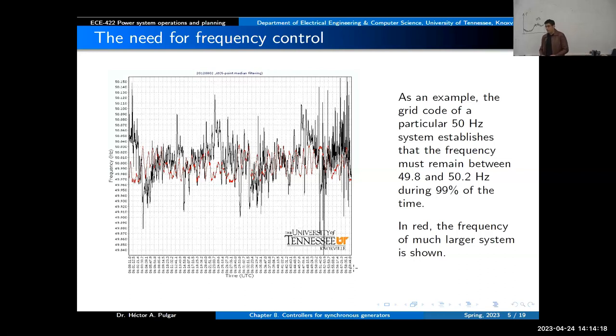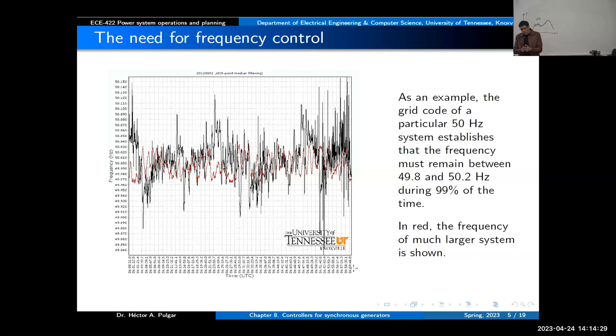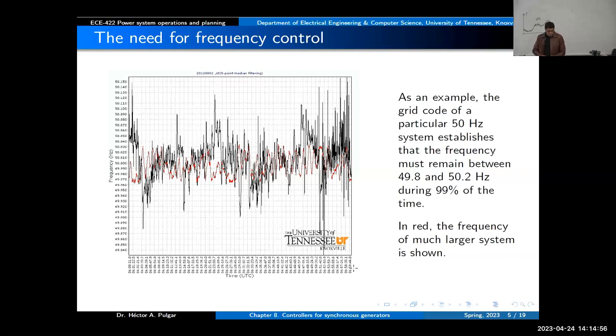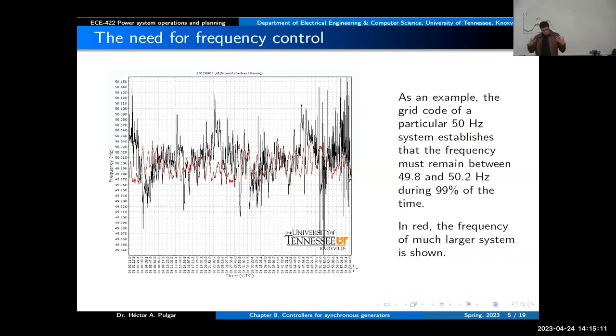Why do we have this difference? The explanation is exactly the energy balance equation shown before. In one case we have more frequency deviation because this is related to kinetic energy. If one system has smaller inertia, then for the same amount of imbalance — the same delta EK — the speed will need to deviate more. But if you have more inertia in the system, for the same imbalance the speed will deviate less.